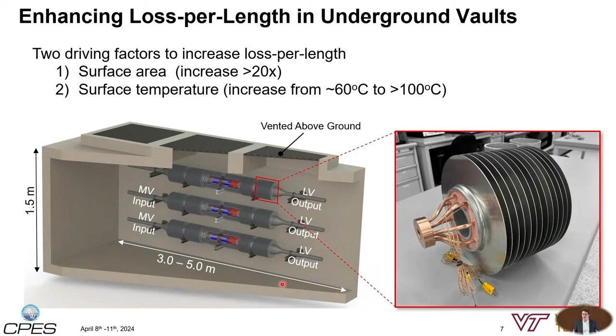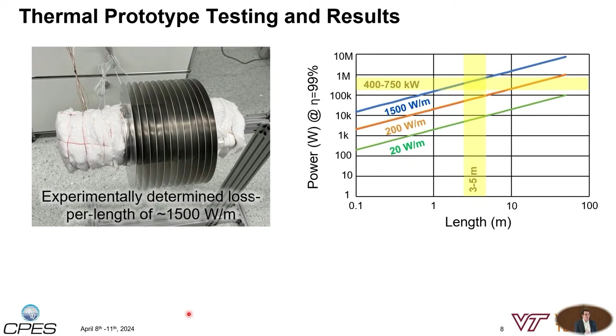So we tested this system here. It tested out about 1,500 watts per meter. If we plot that out as power versus length, for a 3 to 5 meter box at 1,500 watts per meter, you can handle something in the high hundreds of kilowatts range, sub 1 megawatt range, assuming you're at 99% efficiency. That efficiency starts to drop off too much, and you can hit that power requirement pretty quickly. But that's the order of magnitude we're looking at roughly with a thermal system like this.